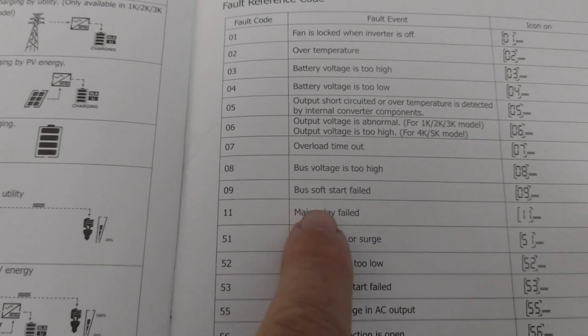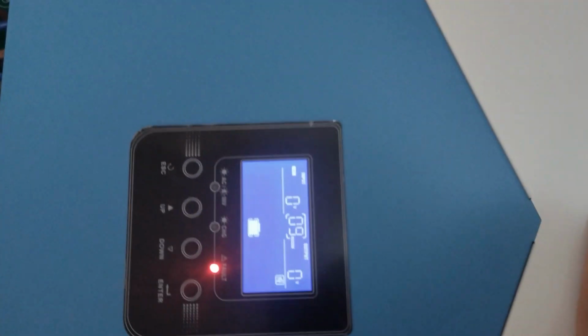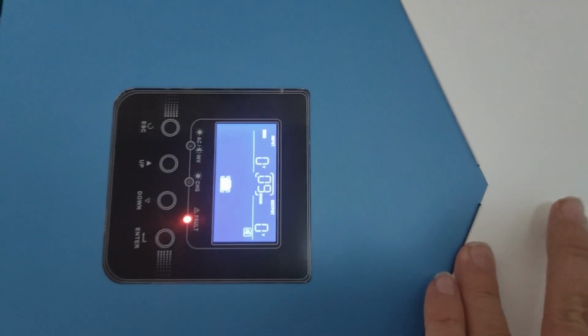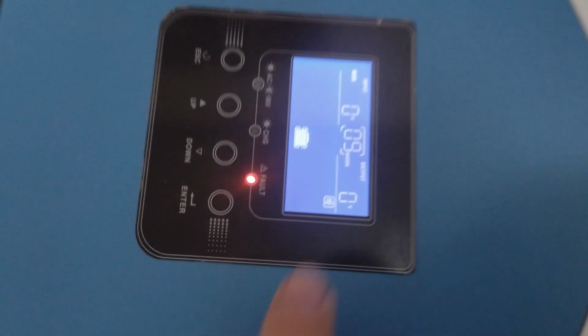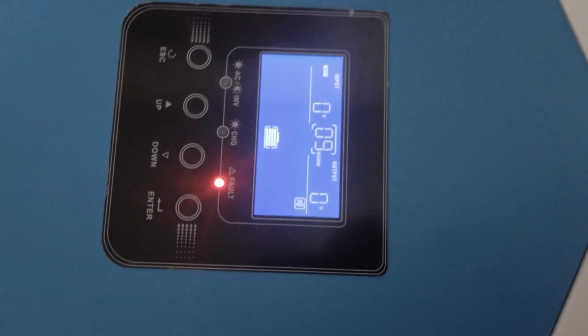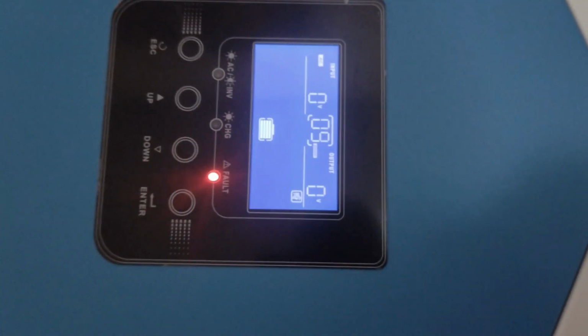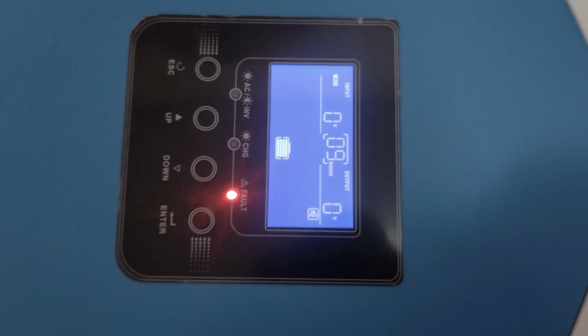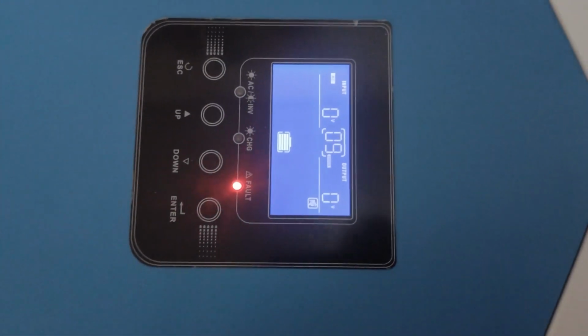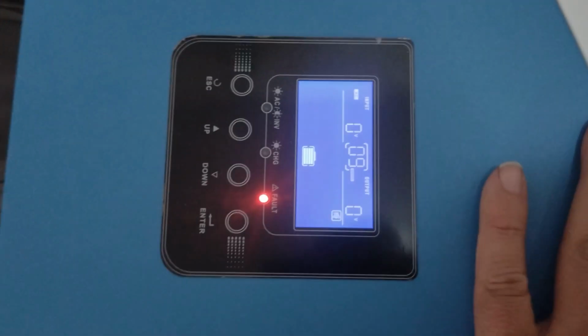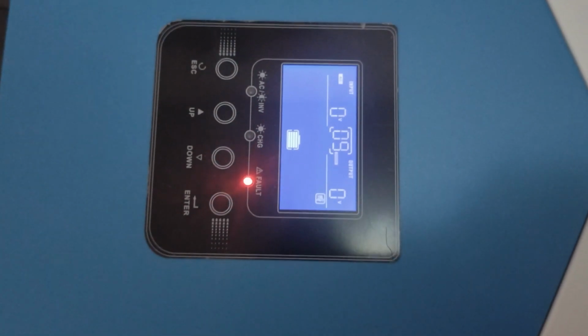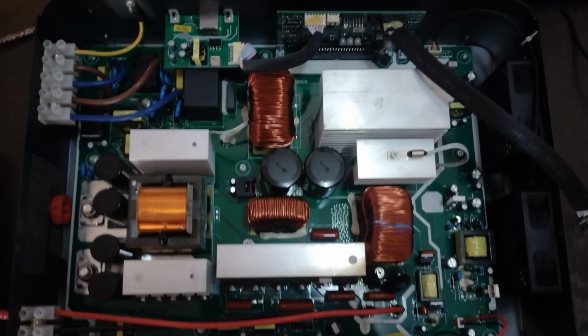Okay, fault 9 is bus soft start failed. That typically means when it powers up for the first time, it'll slowly ramp up the power to the 380 volt bus. And if it can't get a voltage reading, it'll shut down and give error 9. So this usually means there's a dead short across the high voltage bus. This is usually one of the AC output IGBTs have gone bad. So we'll pop the cover off, make sure everything's discharged, and start probing around.